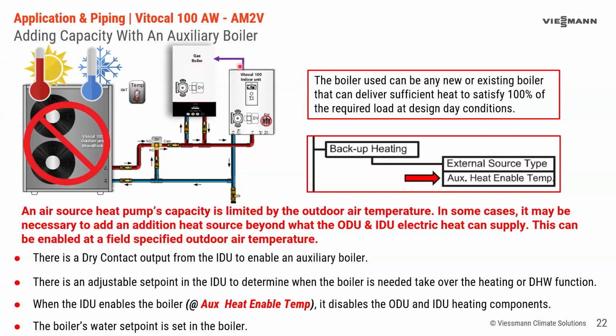Now, also, when this boiler is enabled, when this indoor unit says, hey, boiler, you're in charge, we disable the outdoor unit's ability to move energy, and we turn off the electric heat. So this boiler has to be sized for 100% of your building load. It's not saying, well, the heat pump plus this boiler, the electric heat plus this boiler. This boiler is 100% in charge of the heating of the building when it's switched to that system. So make sure that the boiler you're using is big enough for 100% of the load, whether it's heating or domestic or whatever the larger of the two are. That's what's going to need to happen, okay?